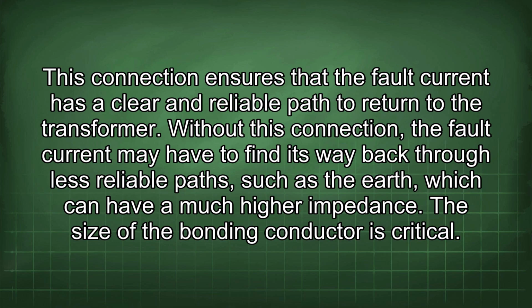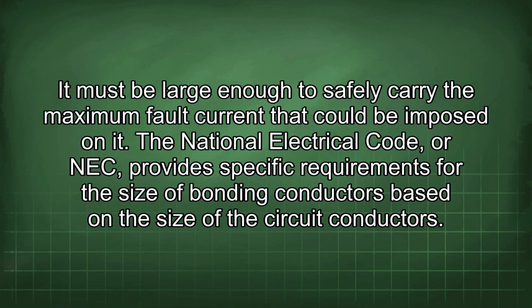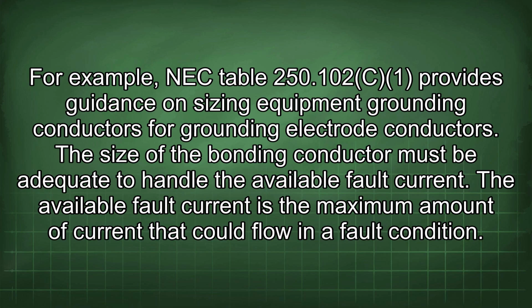The size of the bonding conductor is critical. It must be large enough to safely carry the maximum fault current that could be imposed on it. The National Electrical Code, or NEC, provides specific requirements for the size of bonding conductors based on the size of the circuit conductors. For example, NEC Table 250.102 provides guidance on sizing equipment grounding conductors and grounding electrode conductors.